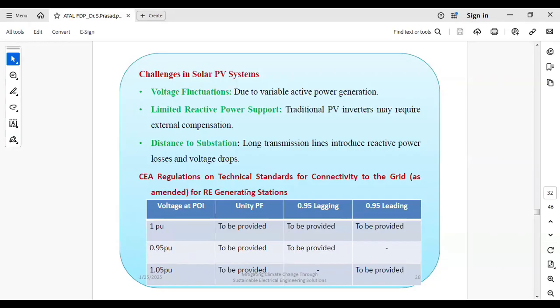Then reactive power can be adjusted by taking the help of the inverter of the PV plant, and also the SVC or STATCOM or capacitor bank installed at the PV plant. But you need to decide, if this much contracted power I need to maintain at the point of interconnection, then what should be the power factor of the inverter? All the inverters have to run at what power factor? Okay, and if this is the power factor of the inverter, then what should be the size of the STATCOM? Minimum, so what is the optimum size of the STATCOM or SVC or capacitor banks I need to install at the PV plant to fulfill the requirement at the grid bus.